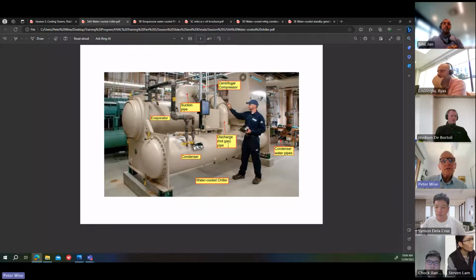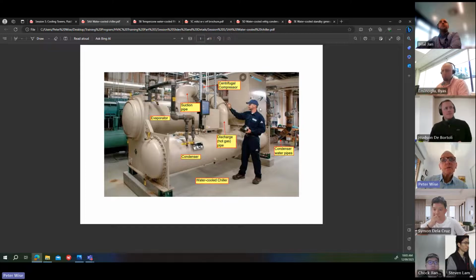In this case, this is the condenser vessel here. The evaporator is up here. The heat from the evaporator is transferred into the condenser, which is a shell and tube heat exchanger. And then water flows through the tubes of the shell and tube heat exchanger into the condenser water pipes, and then off to the cooling tower or fluid cooler or whatever it may be that's rejecting the heat. I'm going to generally refer to these items as a cooling tower, whether it's a fluid cooler or a hybrid cooler. The general parlance in the industry is to call it a cooling tower, but we'll talk about the differences with those.